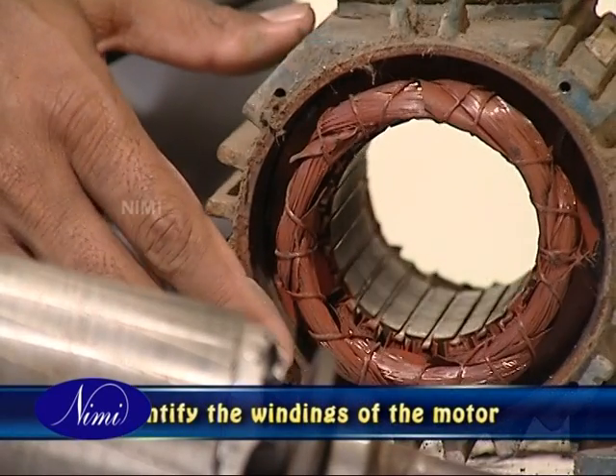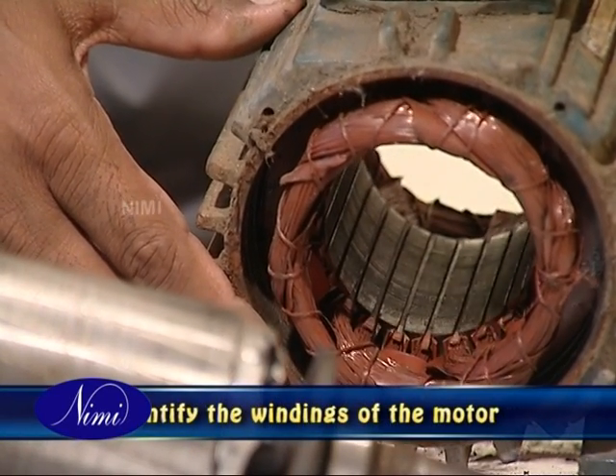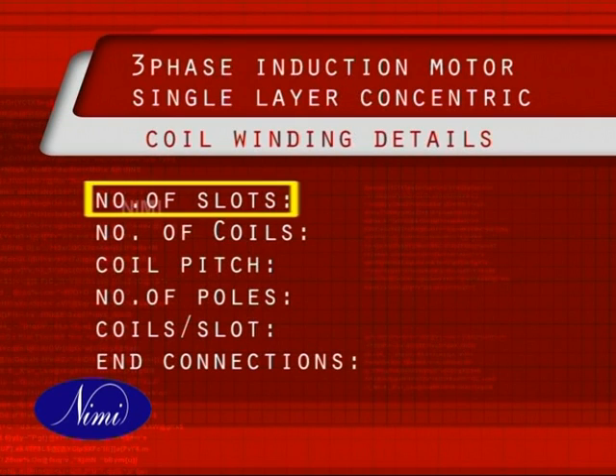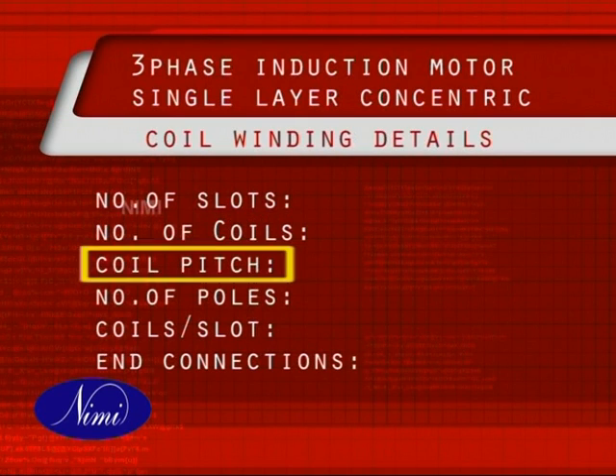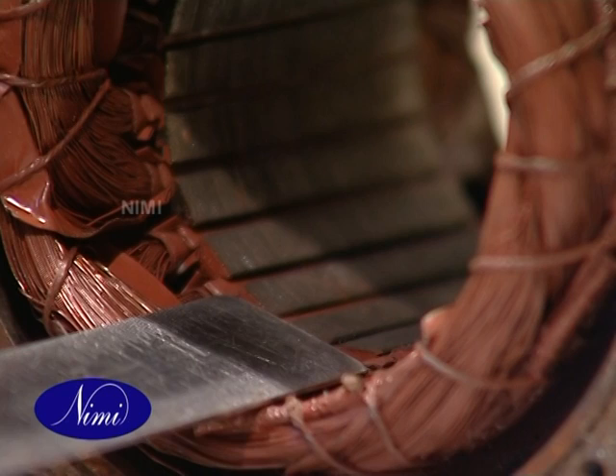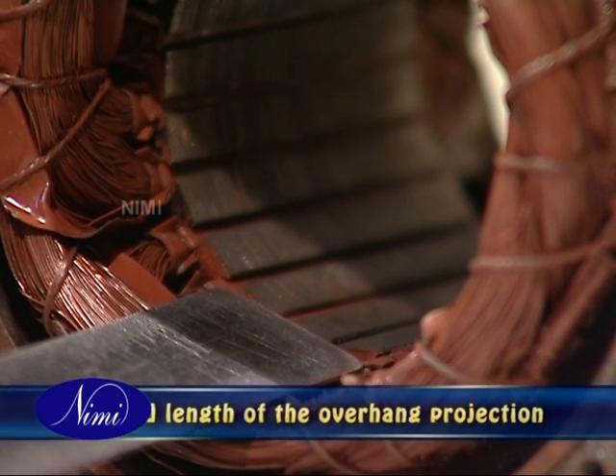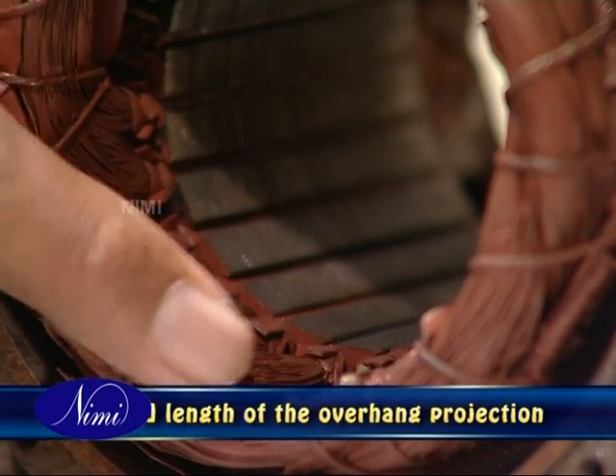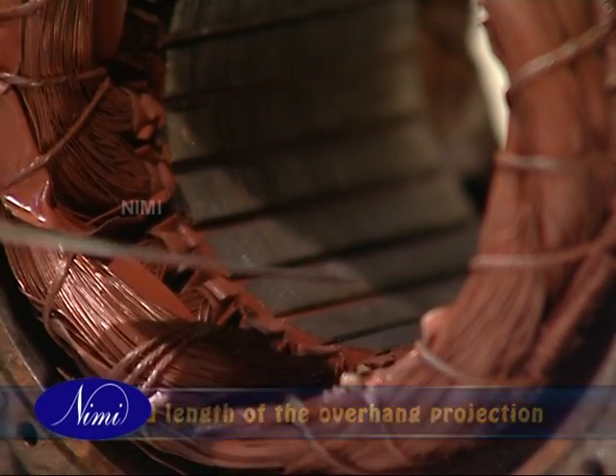Identify the windings of the motor and confirm it is a single layer concentric winding. Record the number of slots, coils, and pitch of the coils in the table. Trace the end and lead connections and make a drawing of the same. Next, record the length of the overhang projection and prepare a template to check the overhang after the rewinding is done.